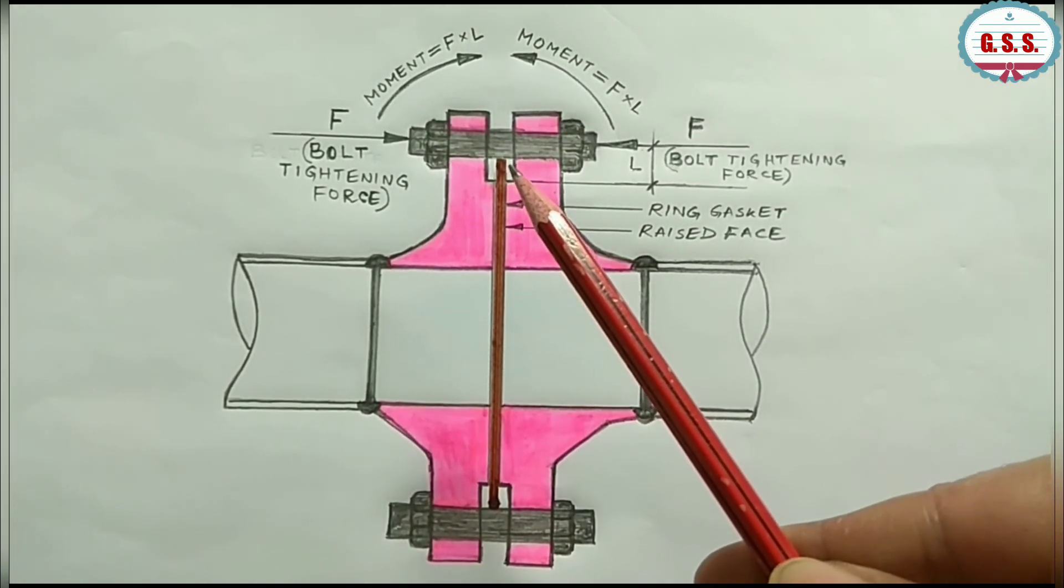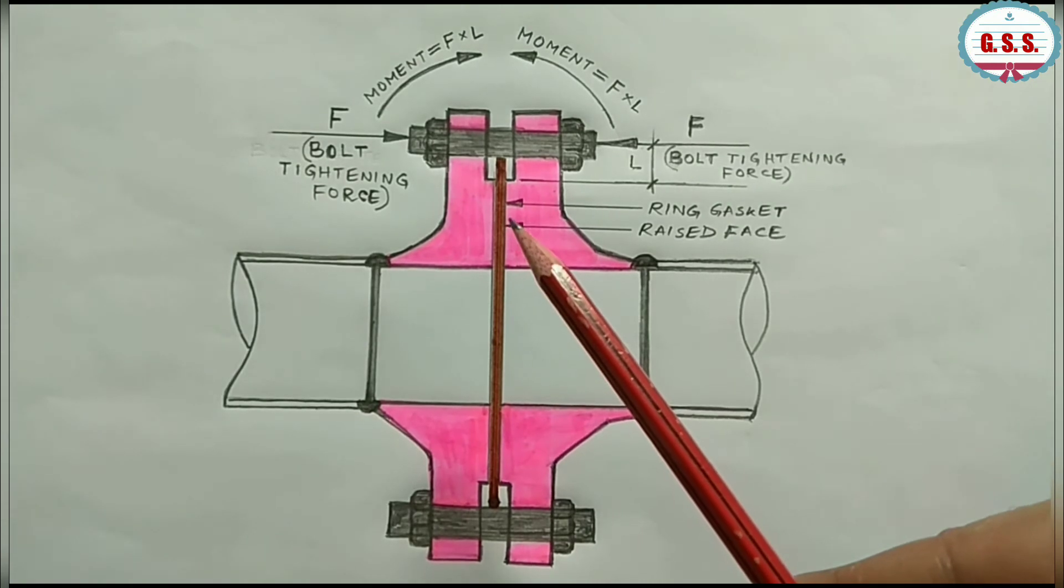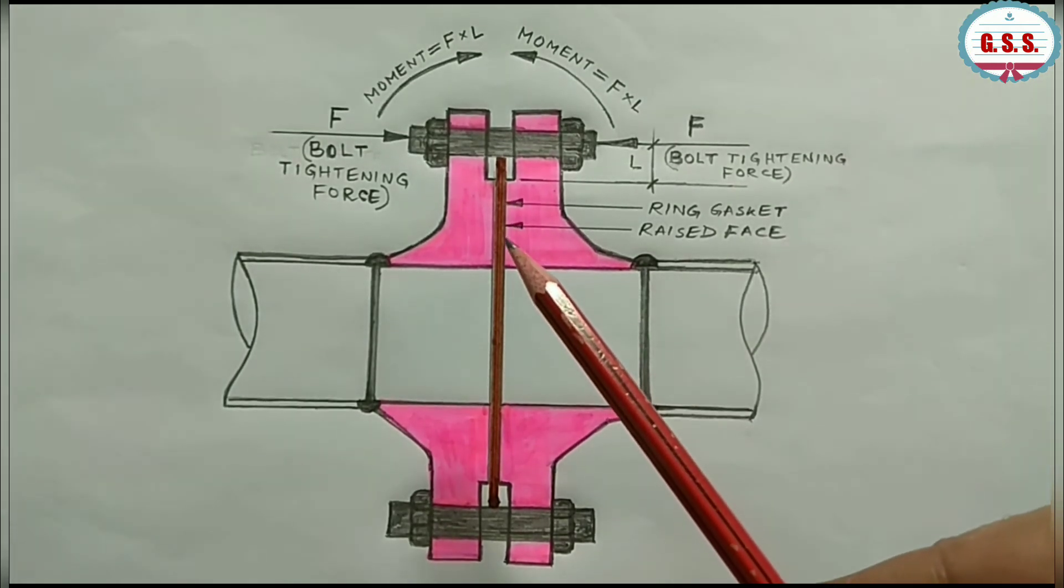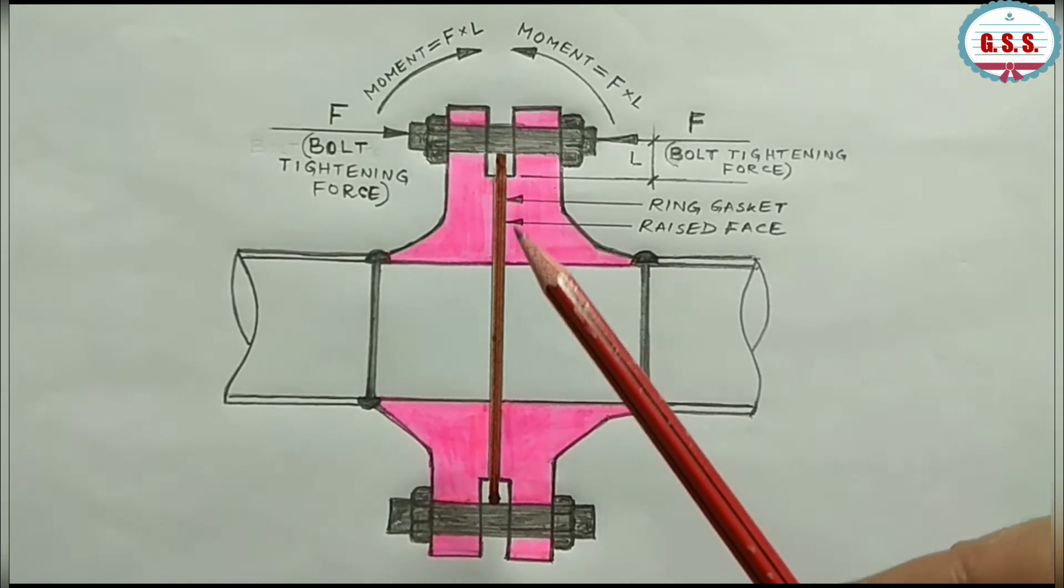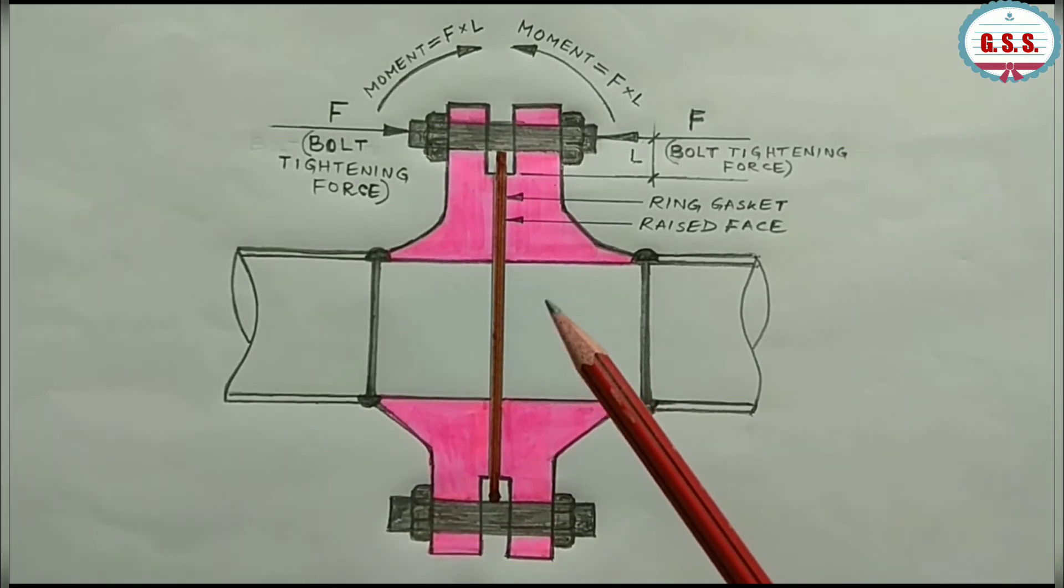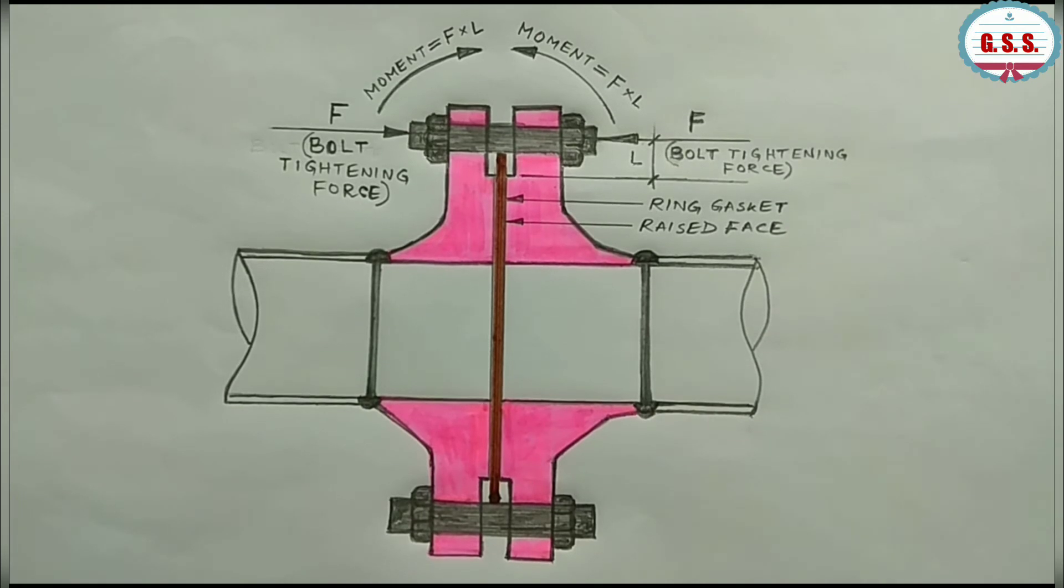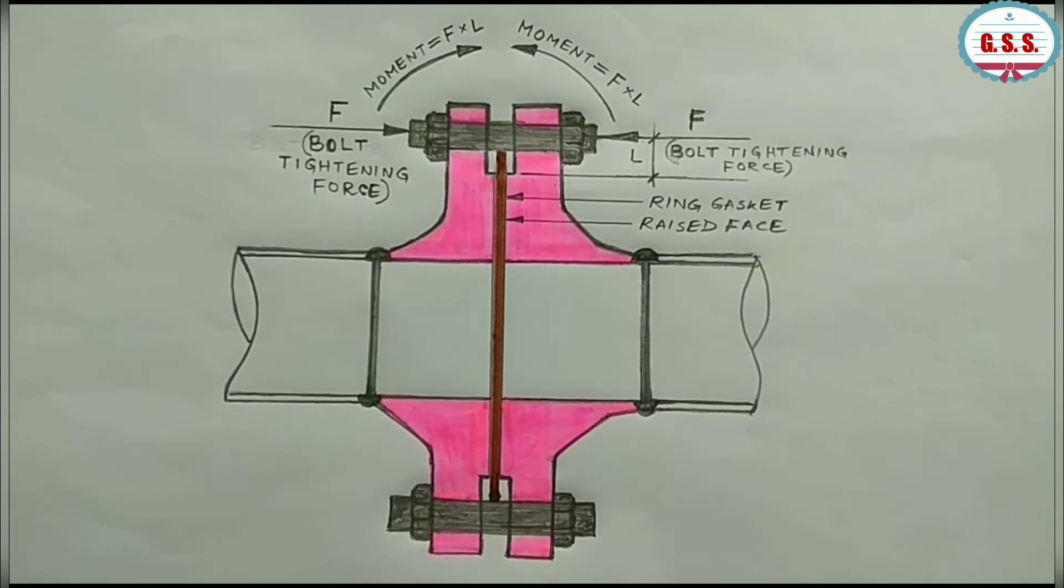The purpose of raised face is to concentrate more pressure on a smaller gasket seating area to achieve more pressure retaining capability of the flange joint, so that the chance of leakage is very less.